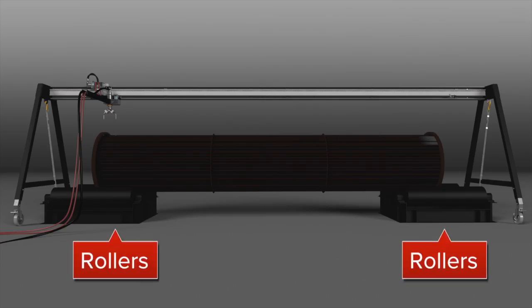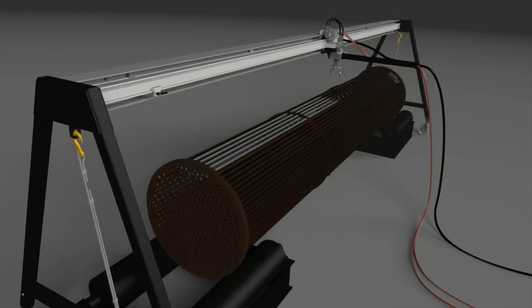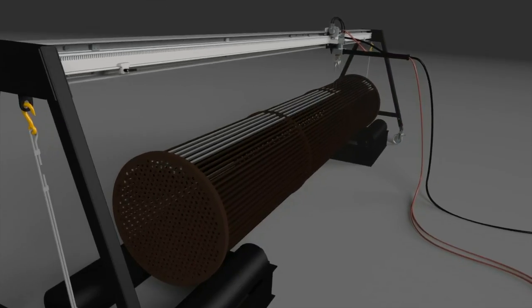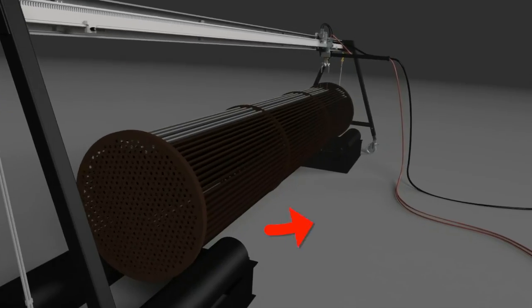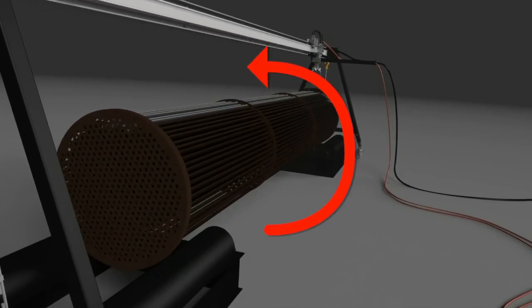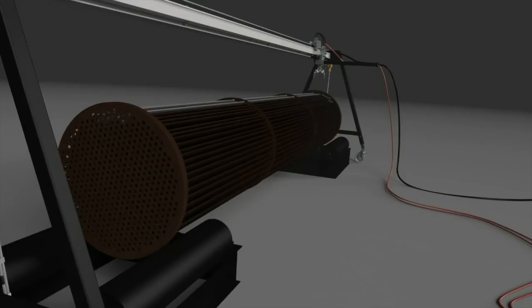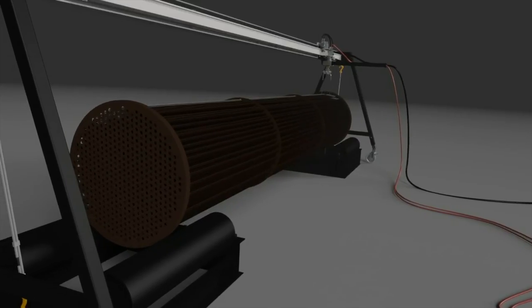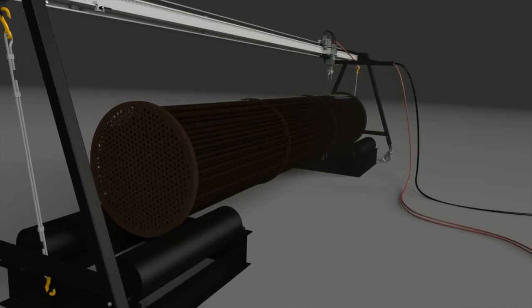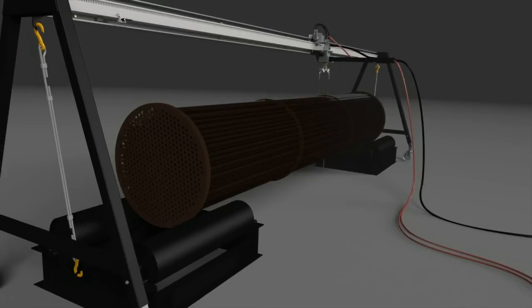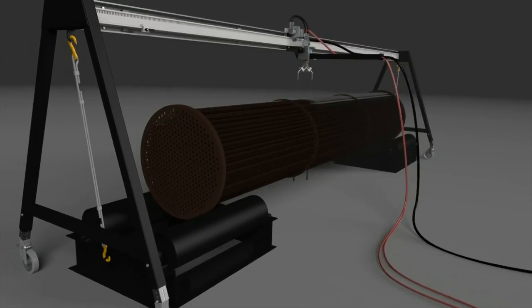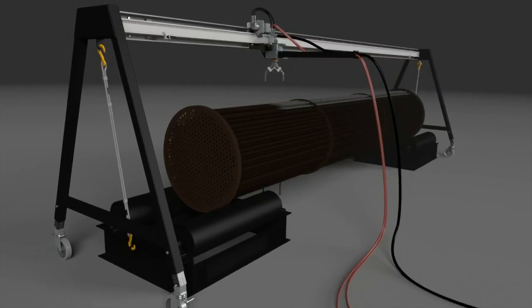The BundleBlaster can be paired with a set of rollers used to rotate the bundle for cleaning. The rollers are designed to fit many bundle sizes. They are engineered for controlled movement which allows you to rotate the bundle the exact width of your jet path after each pass for consistent cleaning. Our standard rollers are hydraulically powered, so you will want to take that into consideration when deciding whether your BundleBlaster will be pneumatically or hydraulically powered.